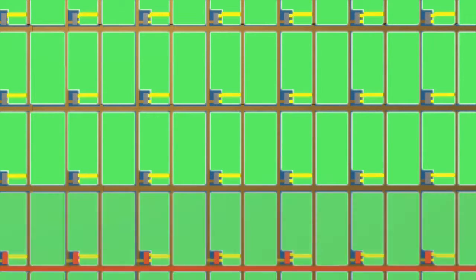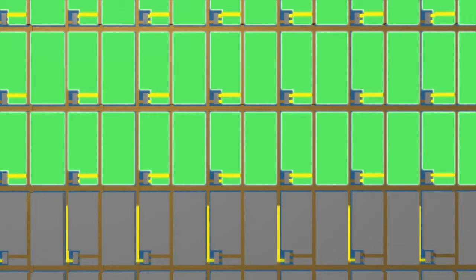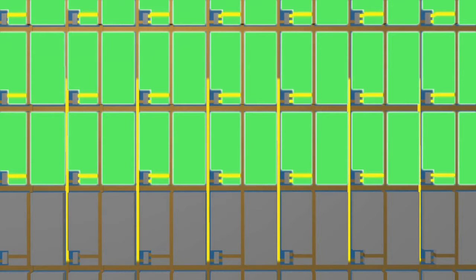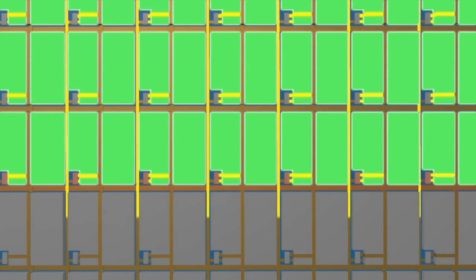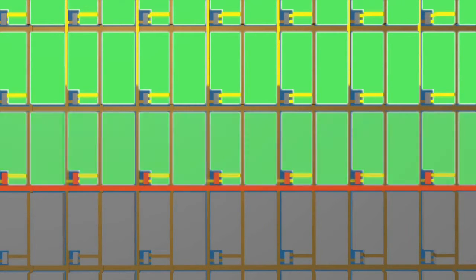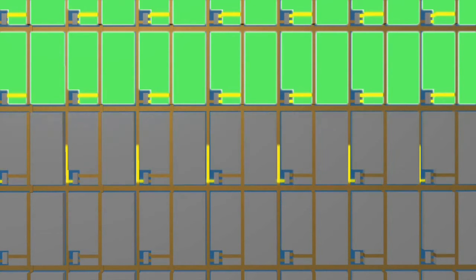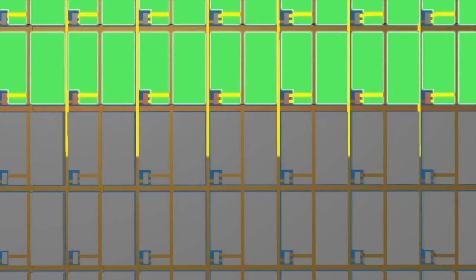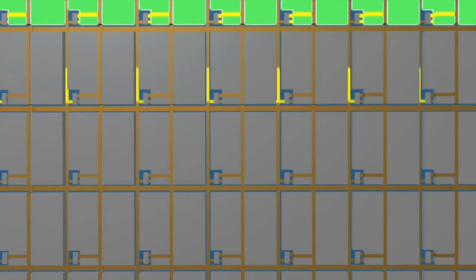Then, a dedicated line turns on the switches, the TFTs, one row at a time, allowing each photo-diode's charge to be recorded. This sequence is repeated one line at a time for the whole array.